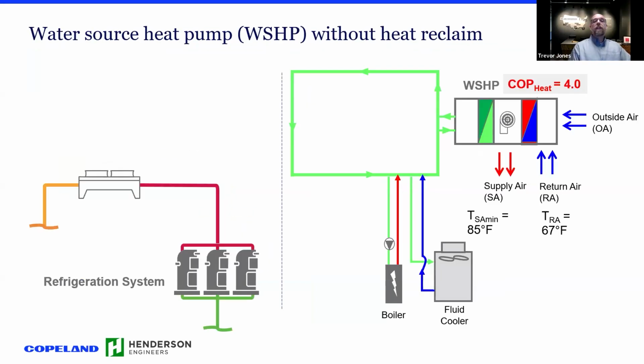So with the water source heat pump system, again, baseline was no reclaim. With the water source heat pump system, you typically have a boiler, pump, and fluid cooler moving heat around within a loop. And then the water source heat pump pulls heat out of the loop or ejects heat into the loop, depending on whether it's in heating or cooling. The typical heating coefficient of performance is 4 for the temperatures that we were looking at for the water source heat pump systems.